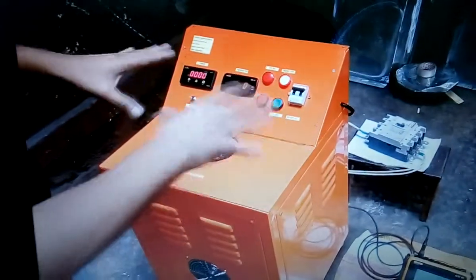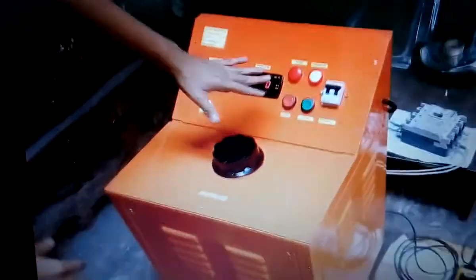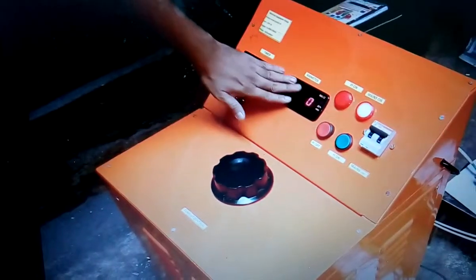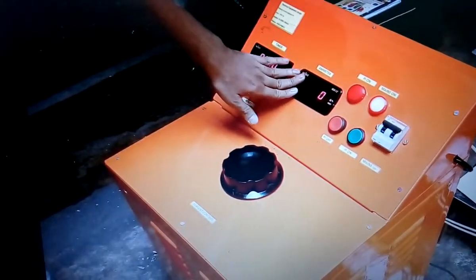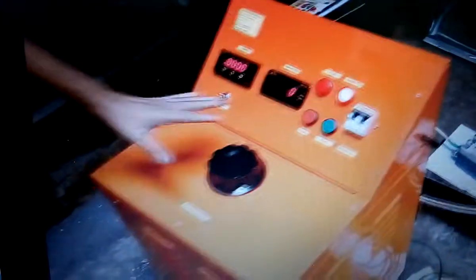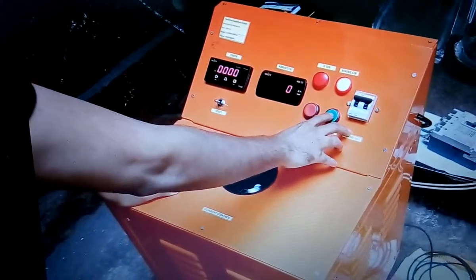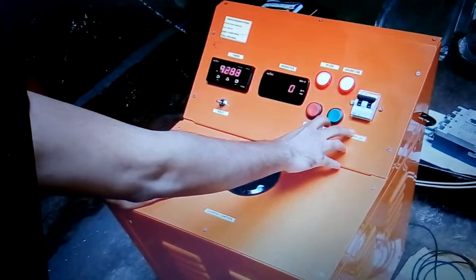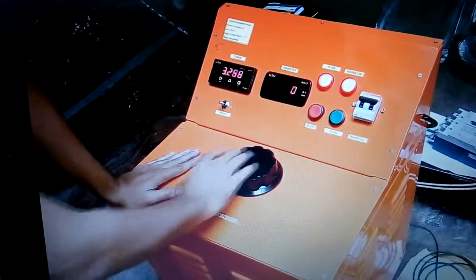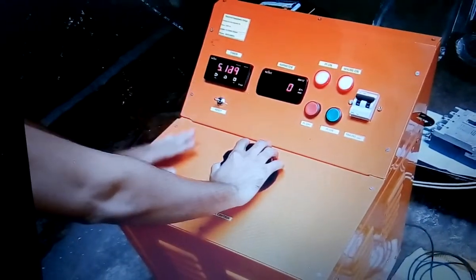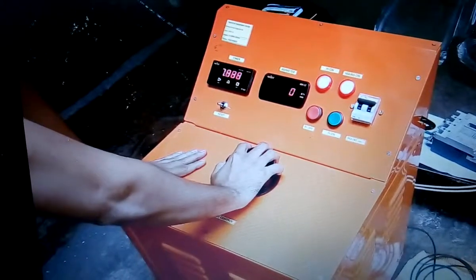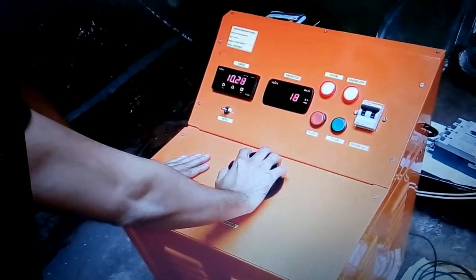So you can see now we have done the setup for testing the MCCB's tripping characteristics. The MCCB is connected over here. Now we are going to inject the current, as I said, 350 ampere or above, so 250% of the normal rated current. We'll start the procedure. Now I'm making it on. So now the primary injection kit is on. The timer has already started, and now we are varying the current and gradually increasing it to 350 ampere.